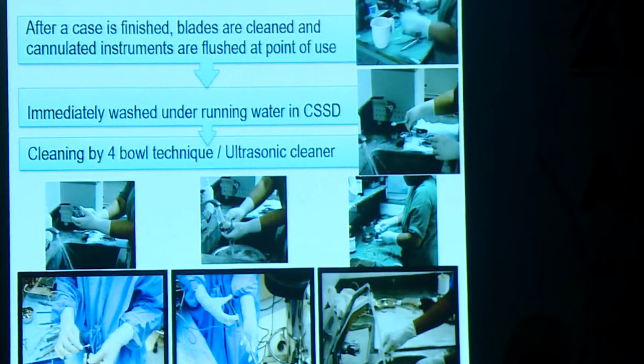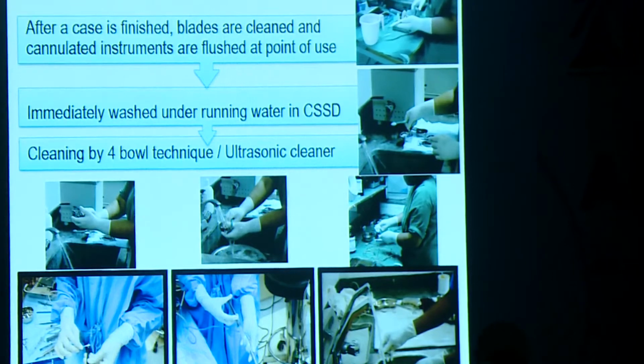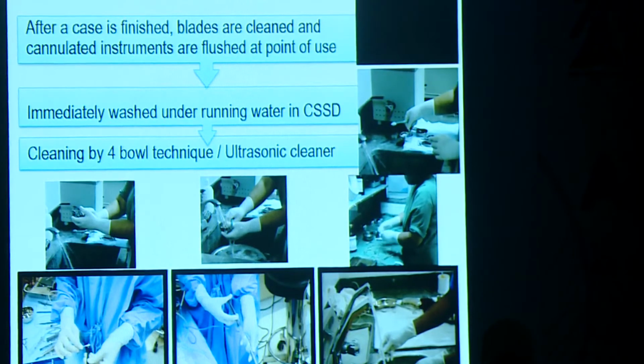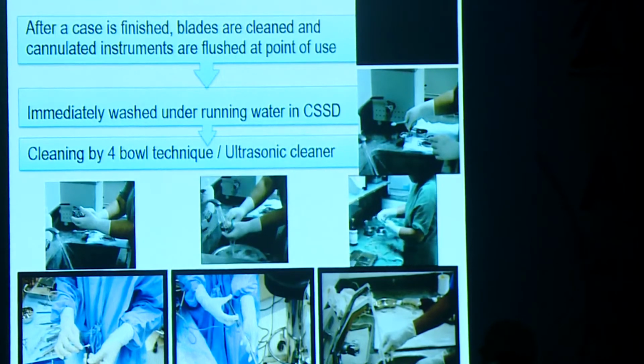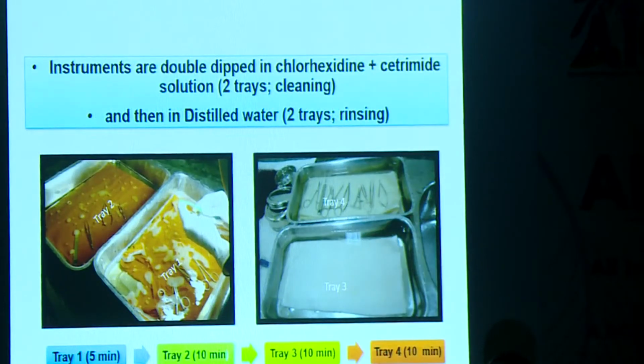After a case is finished, blades are cleaned and cannulated instruments are flushed at the point of use, and then immediately washed under running water, followed by cleaning by the 4-bowl technique or in an ultrasonic cleaner. The instruments are double dipped in chlorhexidine cetrimide solution in 2 trays for cleaning and then in distilled water in 2 trays for rinsing. So tray 1 5 minutes, tray 2 10 minutes, tray 3 10 minutes, followed by tray 4 10 minutes.